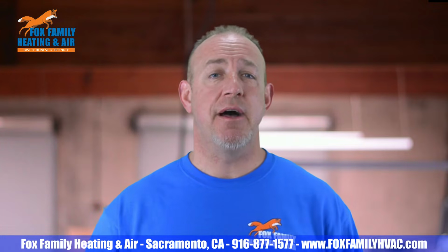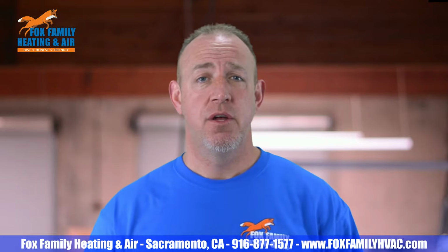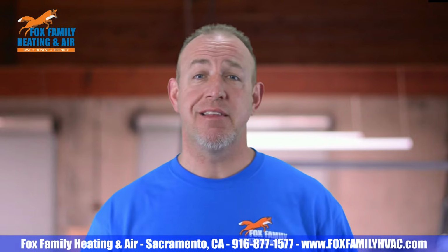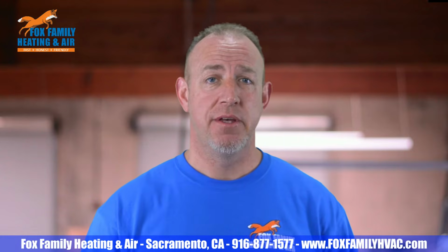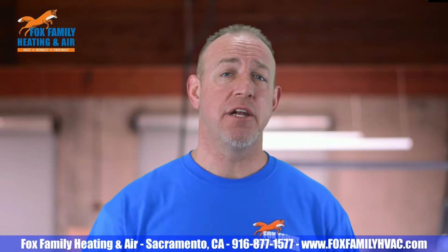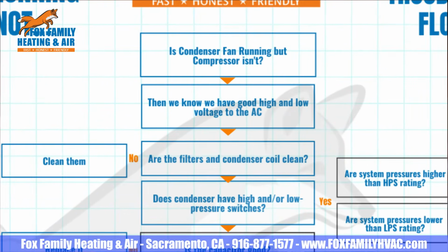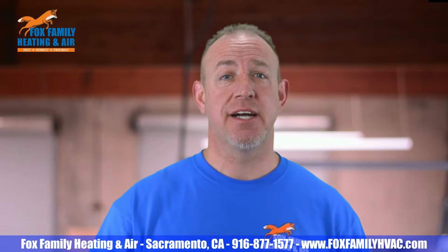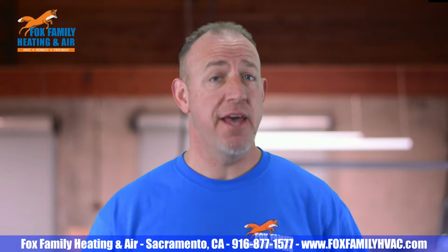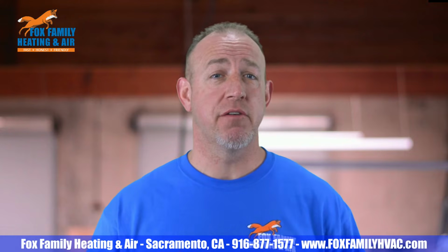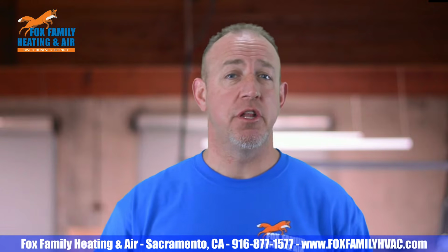Also, I like to tell the customer that I'm going to find and fix the first problem I see. Once I fix it, then I'll run the system again to see if anything else in the sequence of operation is not running right. It's a nice caveat to mention so that they don't think that you're trying to rip them off. Is the fan on top running? Then that lets you know that your high voltage and low voltage are good, meaning your thermostat is successfully calling for cooling to the control board at the air handler, and the control board at the air handler is sending that call to the contactor at the condenser. I'm also going to assume that the contactor at the condenser is pulled in because the fan is running.